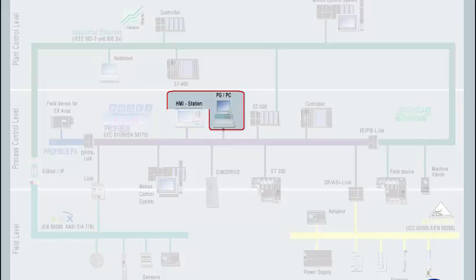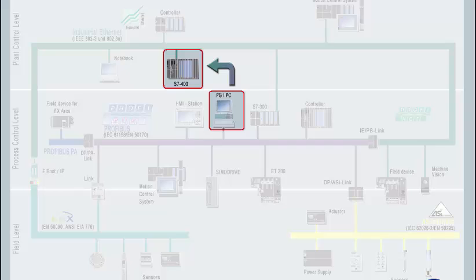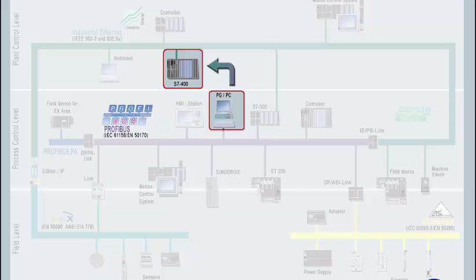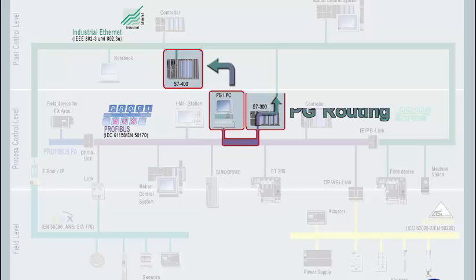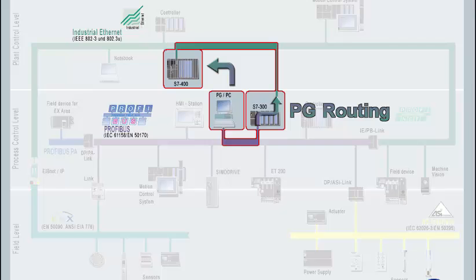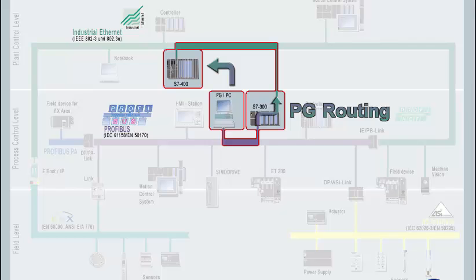As a first example, we are loading a user program into the CPU of the S7-400 station. Due to the fact that the programming device is connected to the PROFIBUS, the S7-400 station on the other hand to the Ethernet bus, the online access is only possible using the operating function PG routing of the S7-300 station.